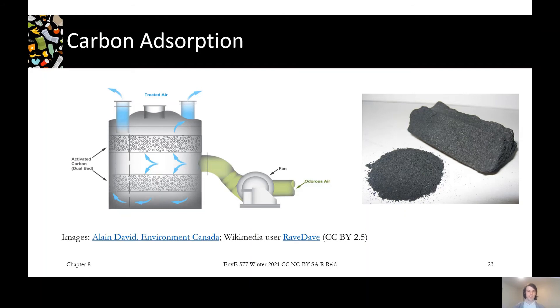You're going to blow your odorous air through, you're going to have really high surface area because you're using granulate or powdered carbon and then at a certain point your carbon is just going to become saturated and it will need to be regenerated or replaced. So pretty straightforward technology, pretty widely applied and really takes advantage of carbon's very good ability to adsorb all types of different organics.